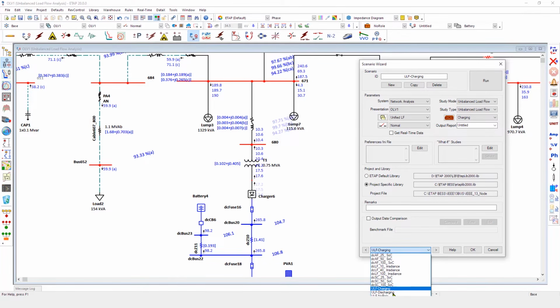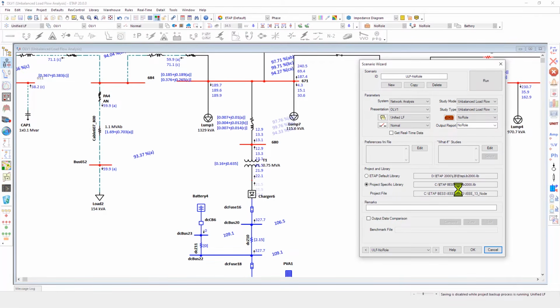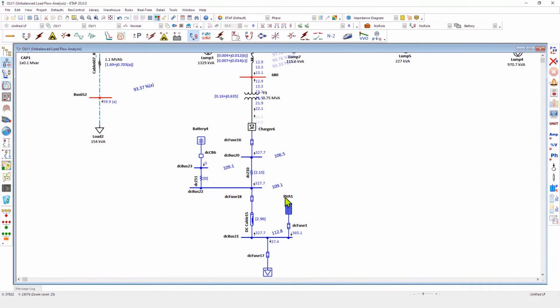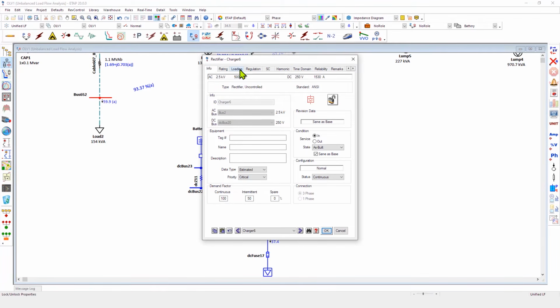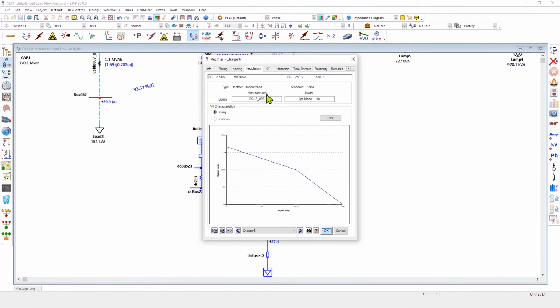The first case, we will essentially leave the load as is and run our unified power flow calculation. Based on this simulation, we can observe that the PV array power is delivering energy into the DC load and also delivering power through the battery rectifier into the AC network. This essentially shows the behavior of this rectifier as a bidirectional converter. In order to set up this rectifier as a bidirectional converter, you also need to set up a regulation curve.